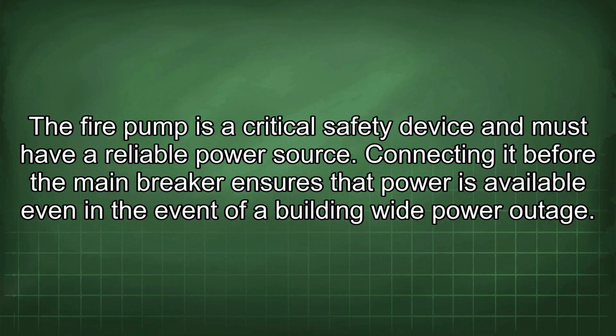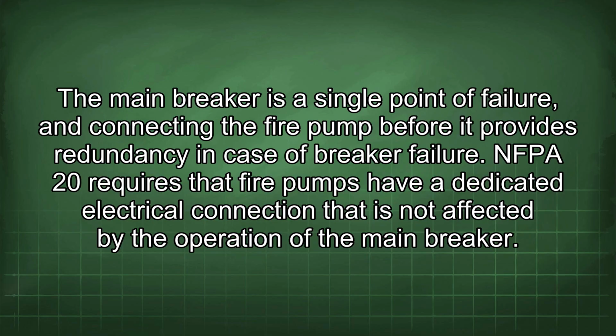The fire pump is a critical safety device and must have a reliable power source. Connecting it before the main breaker ensures that power is available even in the event of a building-wide power outage. The main breaker is a single point of failure, and connecting the fire pump before it provides redundancy in case of breaker failure. NFPA 20 requires that fire pumps have a dedicated electrical connection that is not affected by the operation of the main breaker.